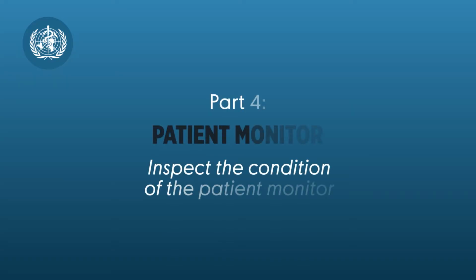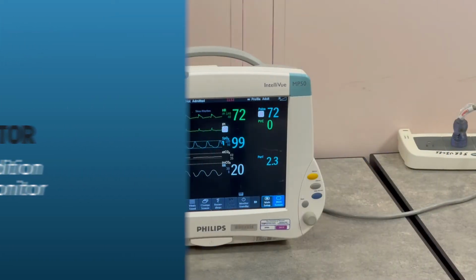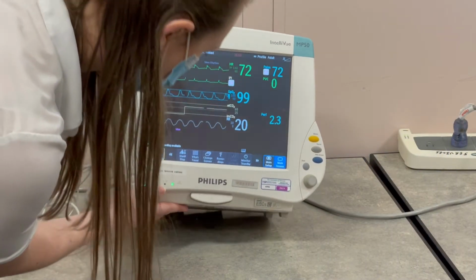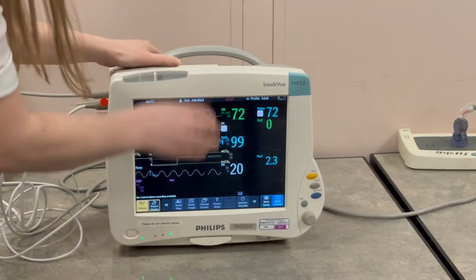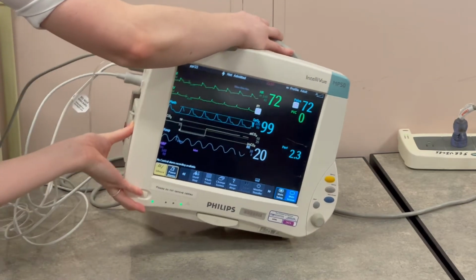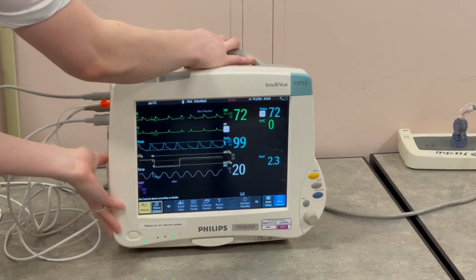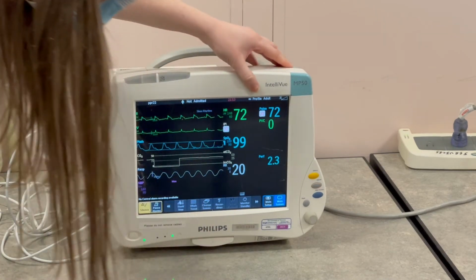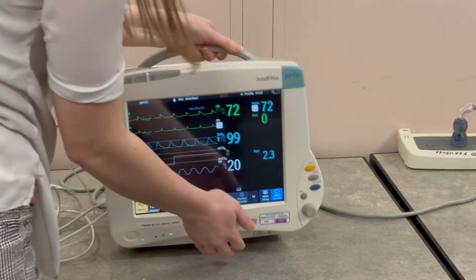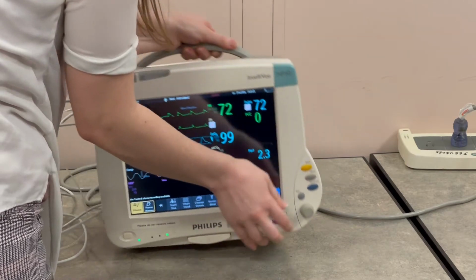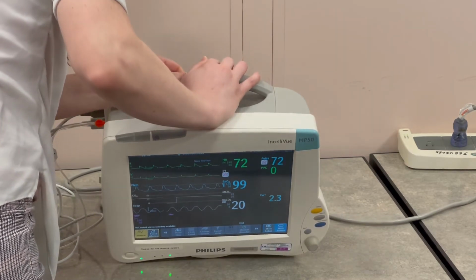Now you are ready to inspect the condition of the patient monitor. Examine the outside of the patient monitor. The visual inspection should evaluate the condition of external hardware such as knobs, display screens, and handles. The device should be clean. Remove any shipping-related protection materials such as screen protectors.